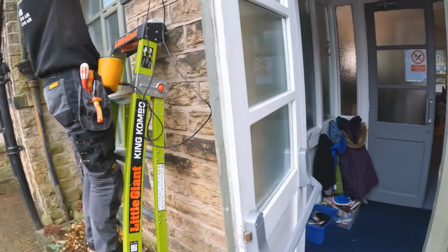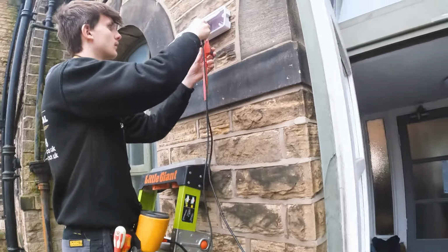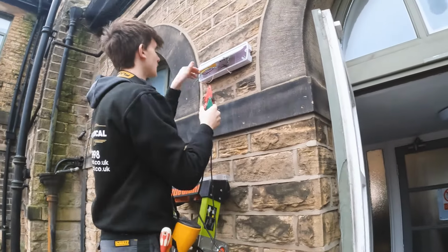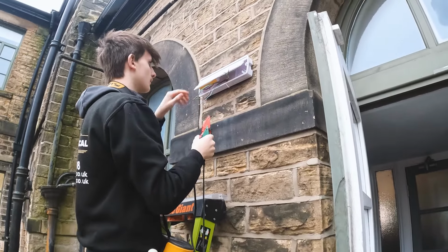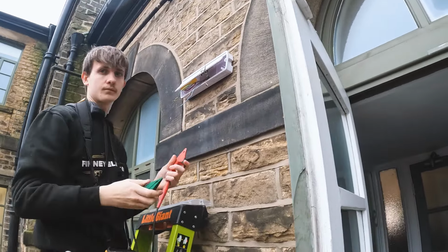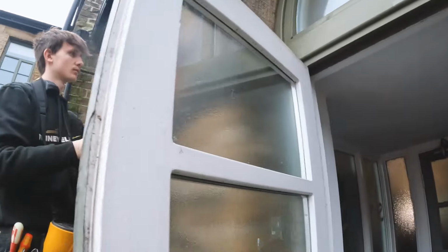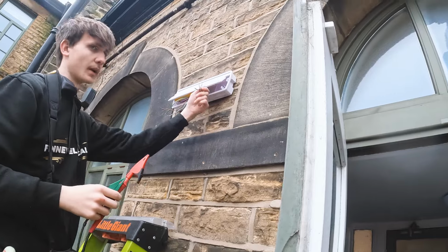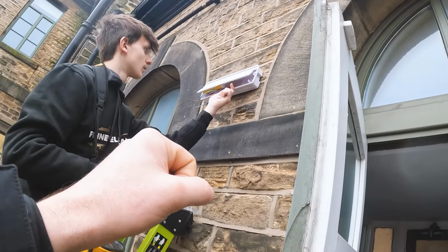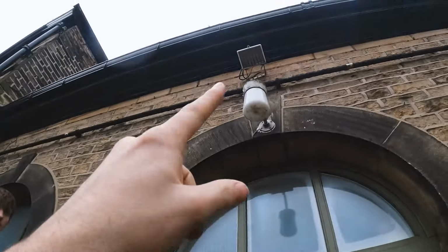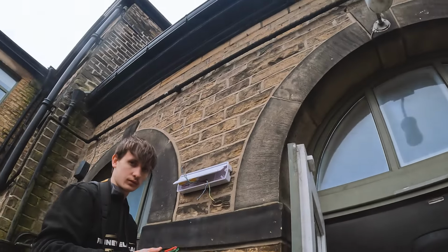Let's do this. Oh, found it. Right then, so we've got a good side, bad side on the emergency lighting. Let's see if that's cleared it though, because we've got a circuit here with a good side and bad side. So if it's clear back at the fuse board, it's whatever cable after that is bad, and it could be on the emergency lighting, you see. Right, so bring that bunch down, so you've got bad cables and good cables. We just noticed we've got these outside lights, but we might need to look into if they're on that circuit. So keep that in the back of your mind.